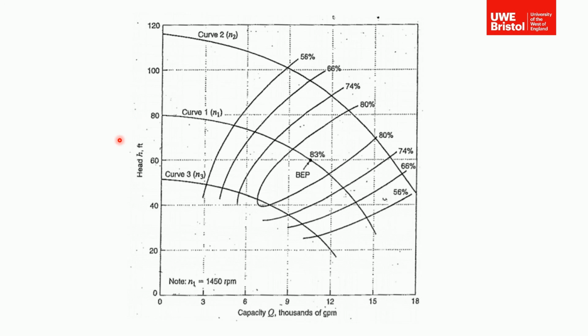Say you're trying to size a pump to lift water up to a header tank in a building. What you really want to know is how high that pump will lift the water in terms of distance, rather than knowing what pressure it is and then having to work out rho g h to find out how high it will lift. So you can see here that, if you want it to lift about 60 feet, at this flow rate, then this is the efficiency and that kind of thing. So pumps are a good example where head is the preferred unit rather than actual pressure.